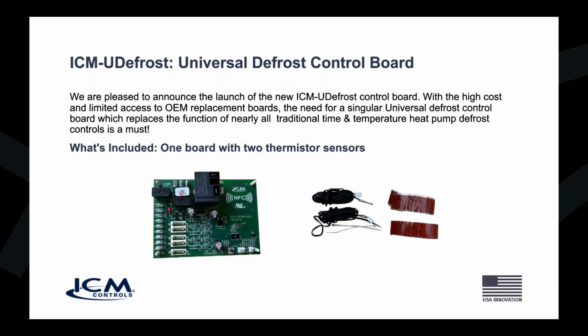So we were pleased to announce the launch of the new ICM-UDefrost control board. There is a high cost and limited access to a lot of your OEM equipment boards, OEM standing for original equipment manufacturers. They can be very costly, a lot of times there are long lead times on them, and sometimes you just can't get them. You need an answer, a defrost board you can go down to your distributor and get, and take care of pretty much any defrost application you could run across, except for demand defrost. We can't do demand defrost with this. That's a special type of defrost, but most traditional defrost can be done with this board.